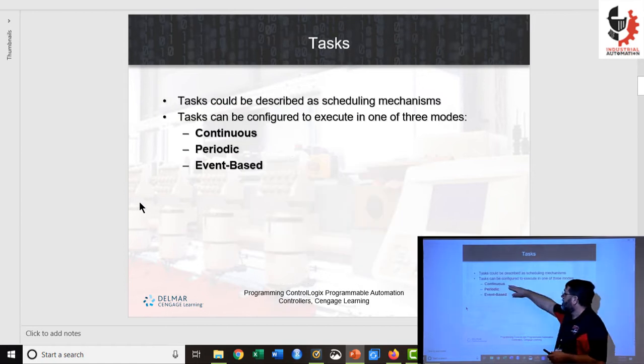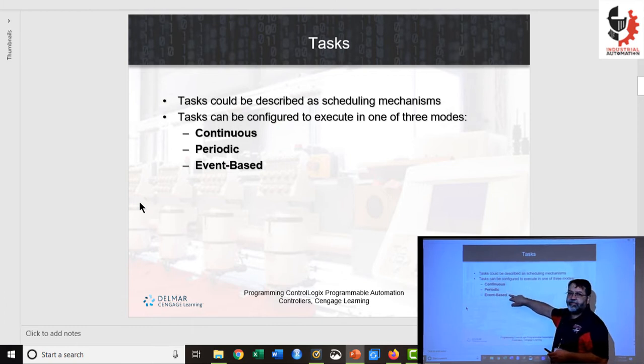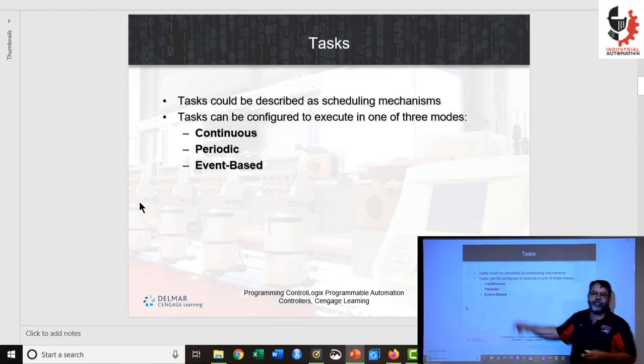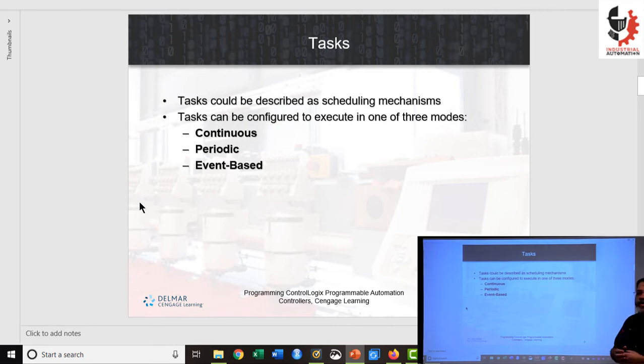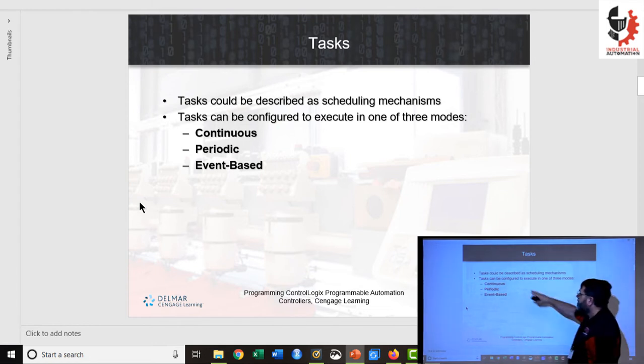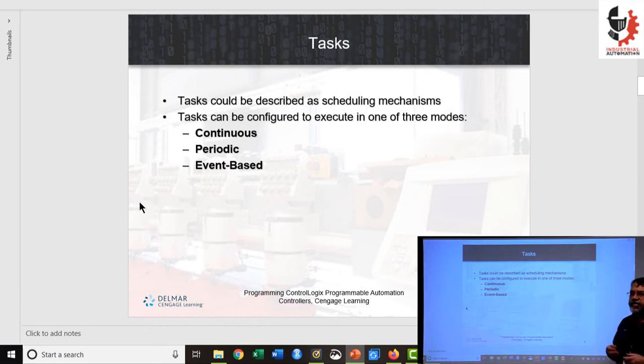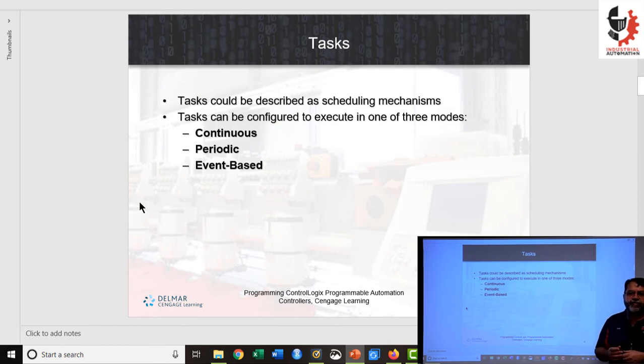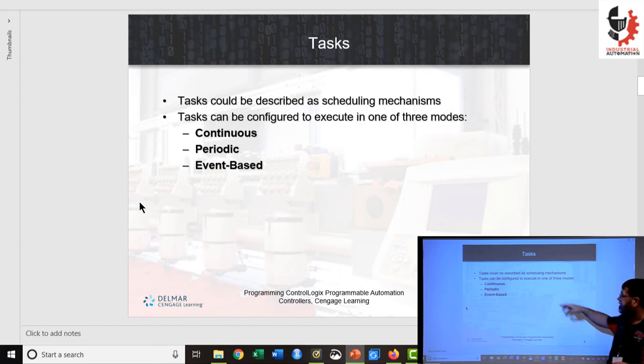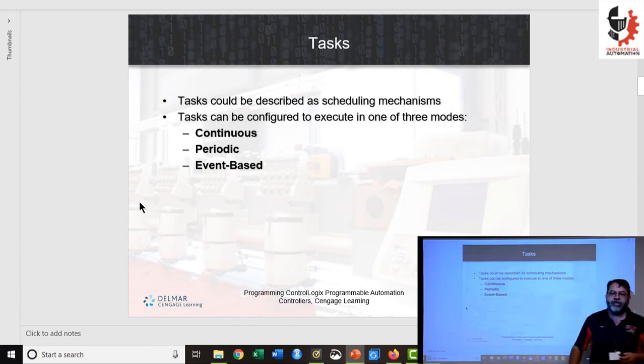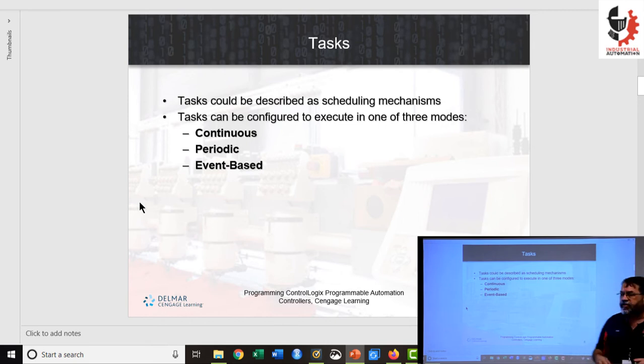We can have three types of tasks: continuous, periodic, and event-based. Continuous tasks run all the time — they're always running and they're the lowest priority task. The continuous task can be interrupted by a periodic task, for example if you want to take a temperature reading every 10 minutes. A periodic task will interrupt the continuous task, do its work, and then the continuous task will continue.